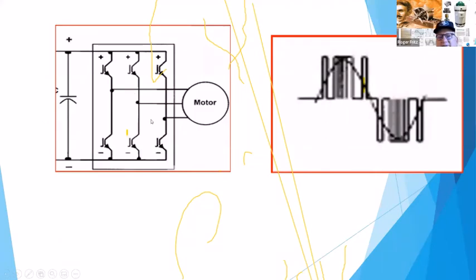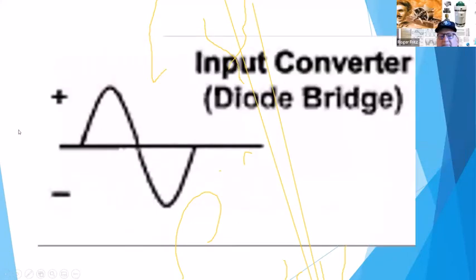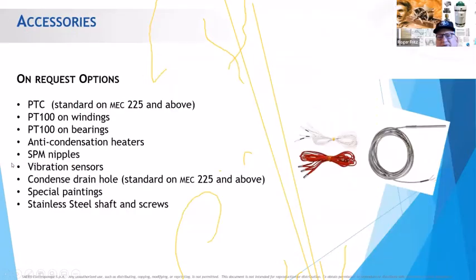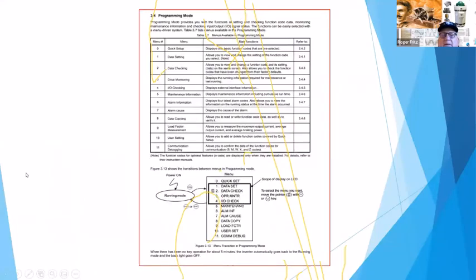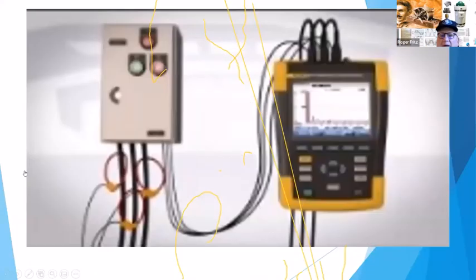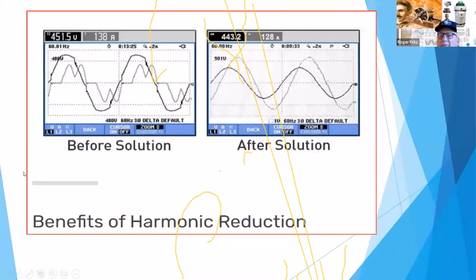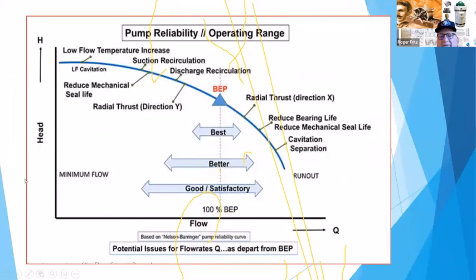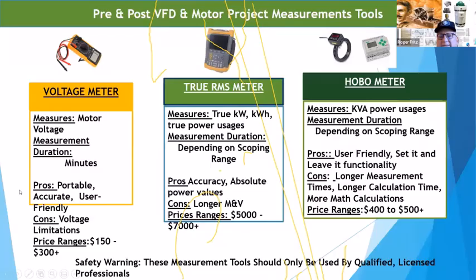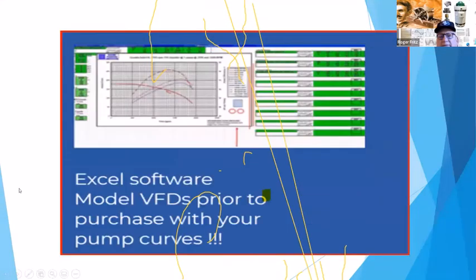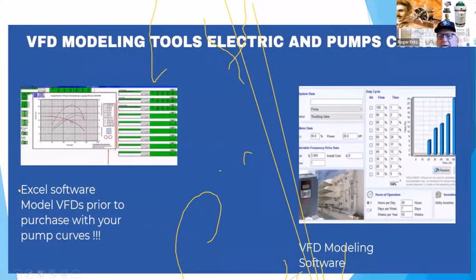You get losses in your transistors, you get losses in your capacitors. It ends up being on average about 3% power loss through the device. Normally it's negligible when you're saving 30%, but it's not when you're looking at total acre feet. So I do highly recommend that you look deeply at accessing this software prior to installing or purchasing a VFD.